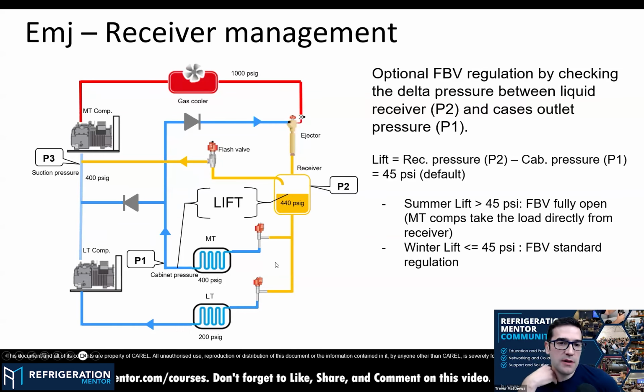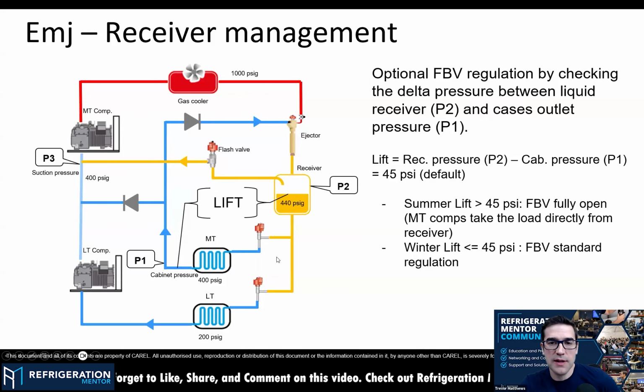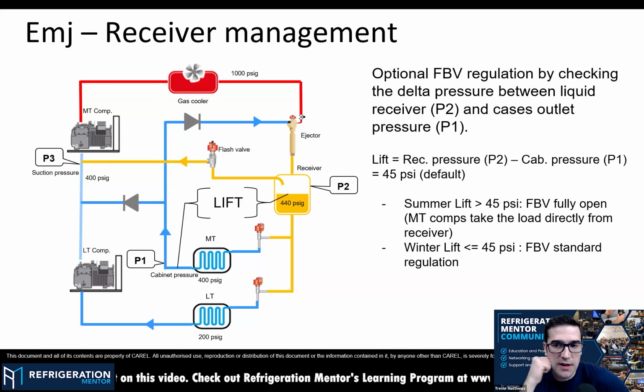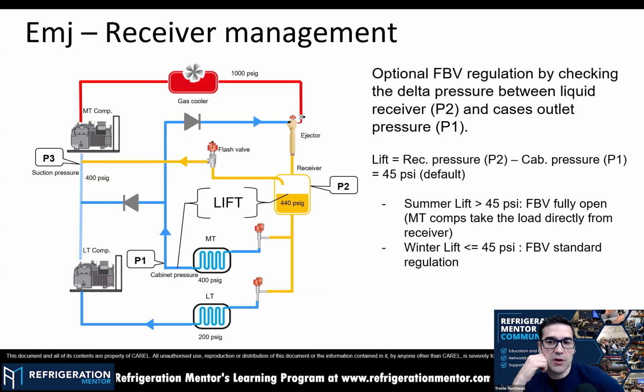That makes sense. Like in the summertime, you're going to want to run that medium temp suction closer to the flash tank, because now you have a higher suction pressure, less work on the compressor, and that's why the flash gas bypass will be open. And then in the wintertime, it's just going to be working as a regular booster system, with the high pressure valve, and the flash gas bypass just maintaining that flash gas pressure to keep flow.